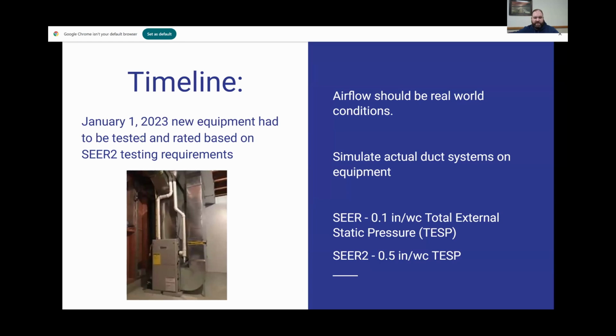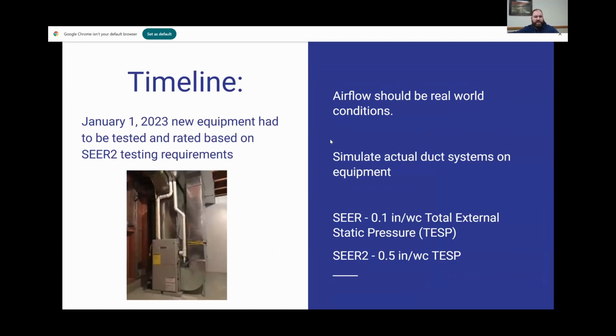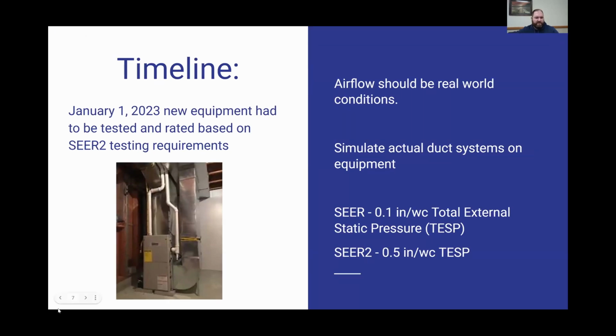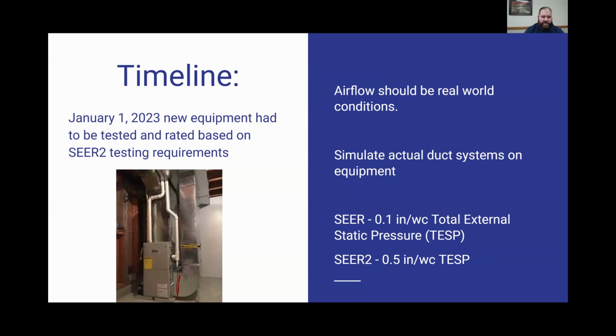I guess I didn't check to see that this would work. Oh, back up one. I used to use a different program when I was teaching like this. Hold that. That's what I was looking for. So the filter on this furnace is going to be right in here. If we were taking the total external static pressure of this furnace, we would go from inside the blower cabinet down here to directly above the furnace here.